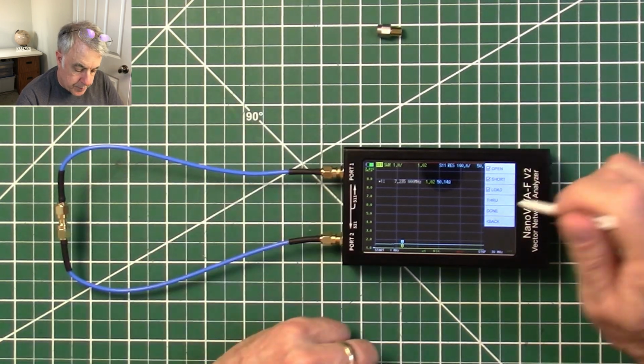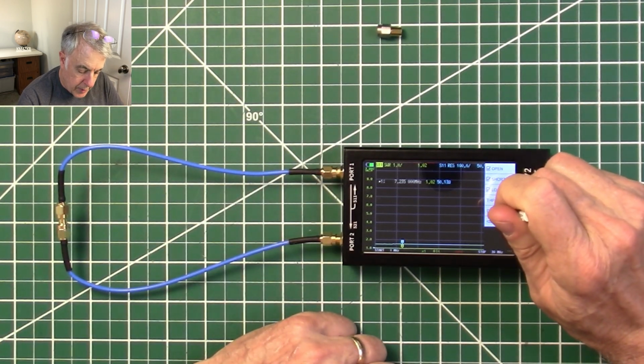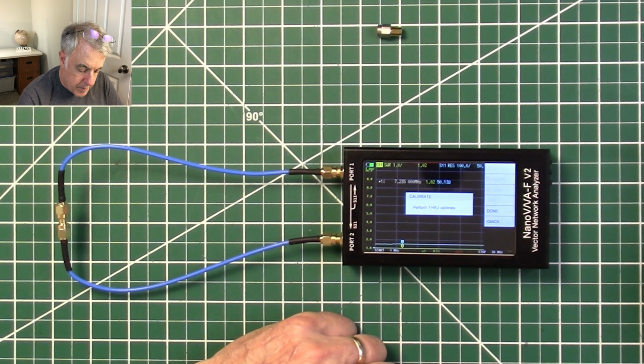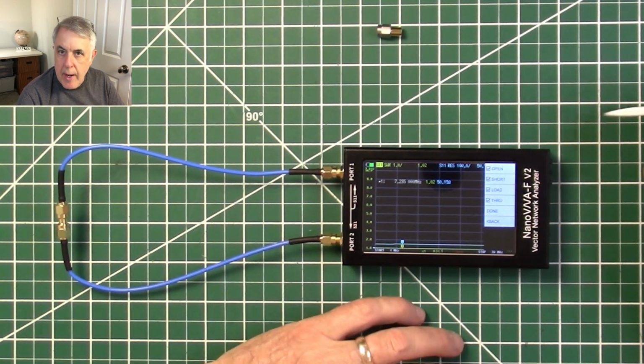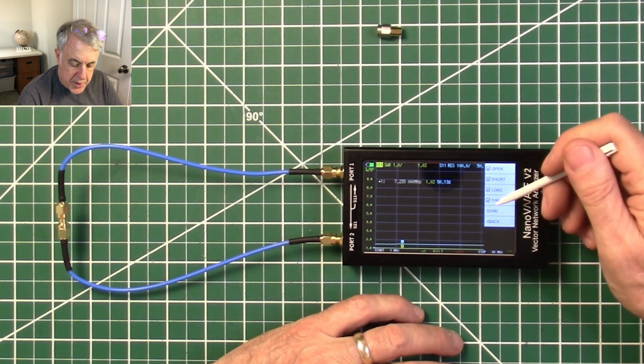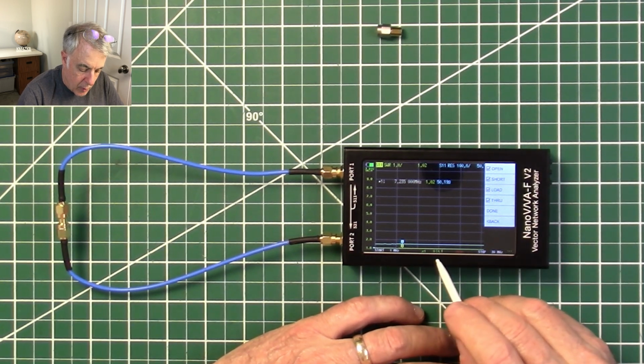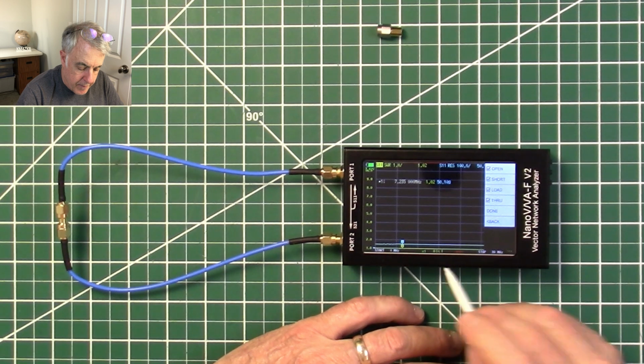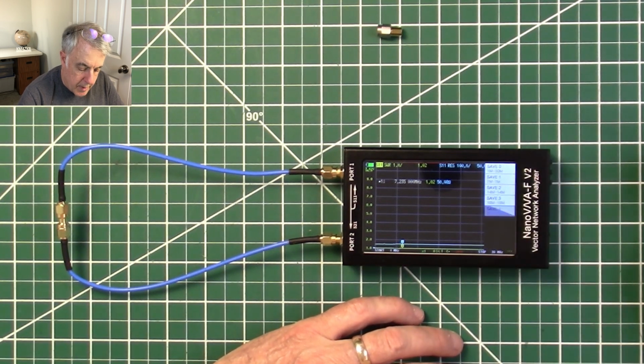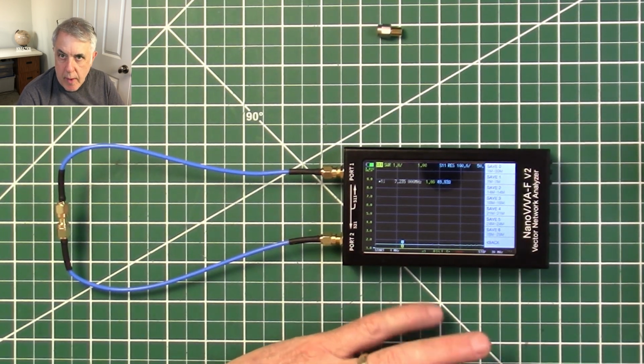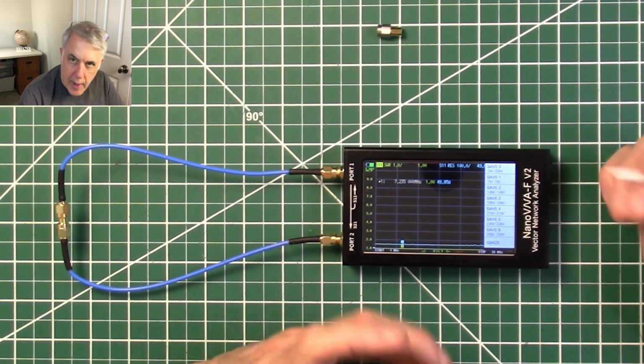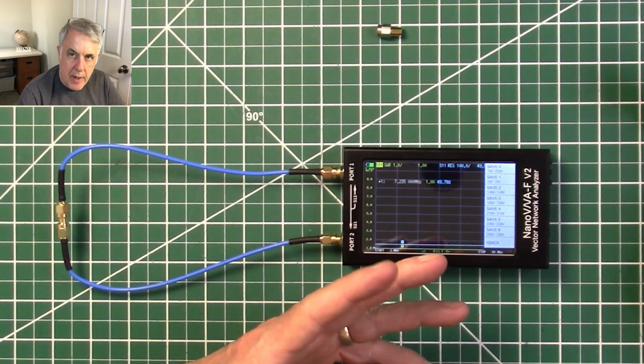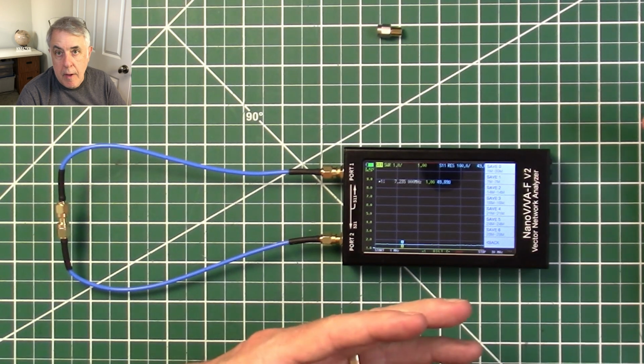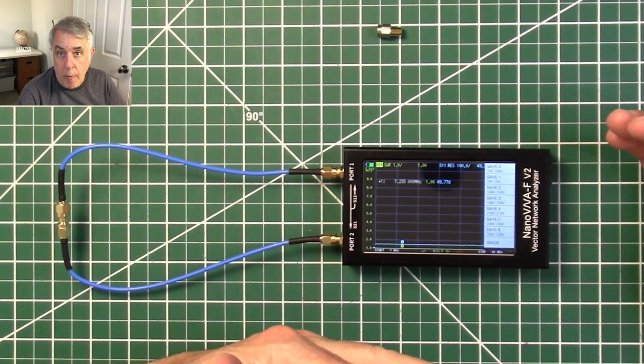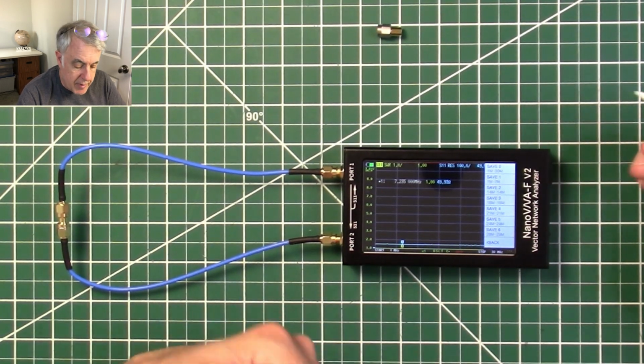So let's click on through, and we've got all 4 of them checked. All 4 of them says they're calibrated right here, but it's not saved anywhere. If we were to turn it off right now without saving it, that calibration would be gone. So we want to save it.